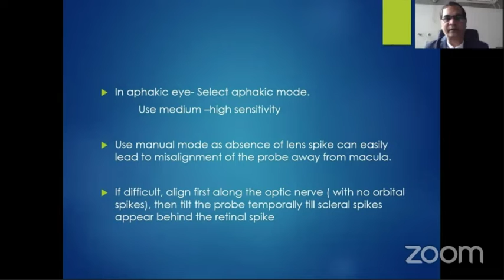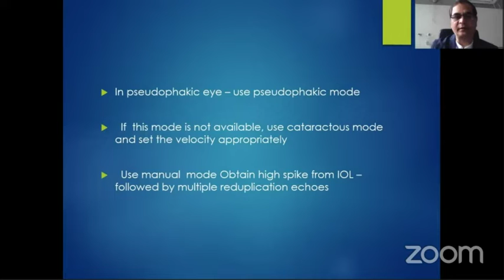In pseudophakic eye, use pseudophakic mode. If this mode is not available, use cataractous mode and set the velocity appropriately. Use manual mode, obtain a high spike from the IOL followed by multiple reduplication echoes.